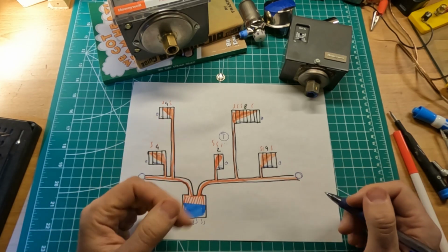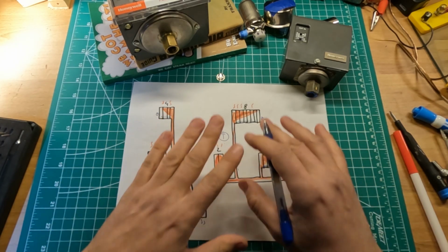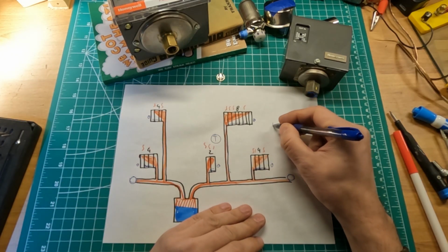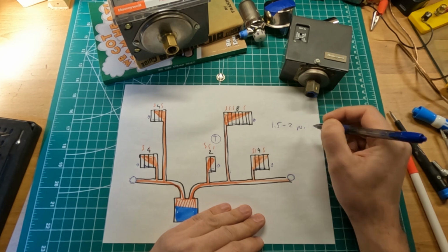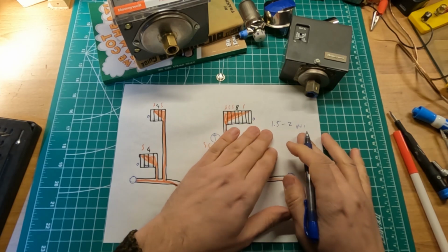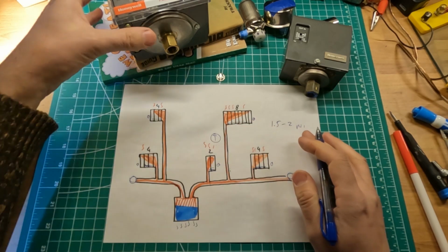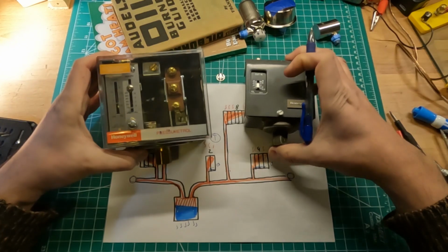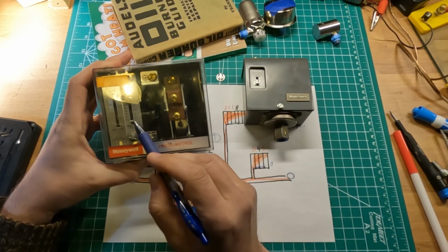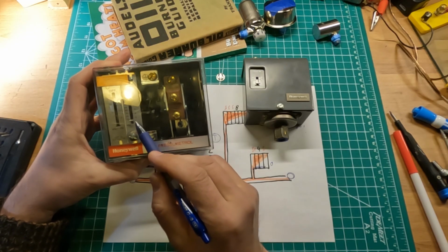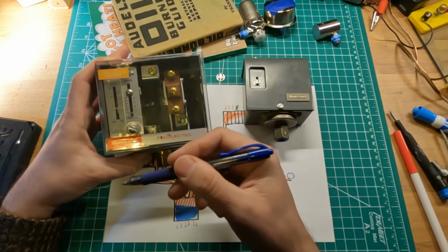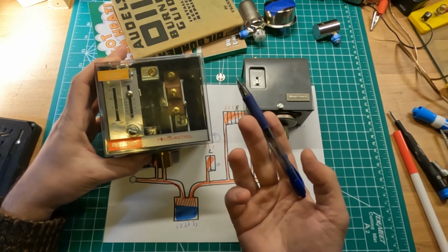So what is that correct steam pressure? The general consensus is that you should set your Pressuretrol to shut down between 1.5 and 2 psi. That's a lot. Again, there are reasons why this setting was chosen, and partially it's because those Pressuretrols are notoriously not particularly precise at such low levels. For instance, this Pressuretrol doesn't even have 1 psi set. The scale starts at 2. There's a line indicating 1, but quite frankly, the manufacturers probably didn't add a number for it on purpose, because they knew we don't know whether it's 1, half a psi, who knows.